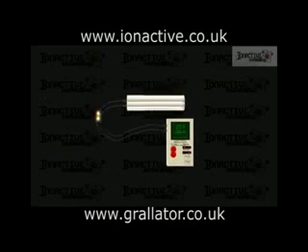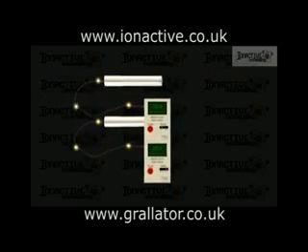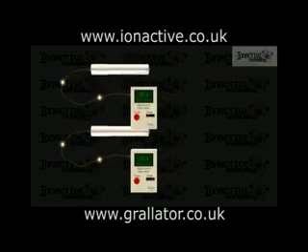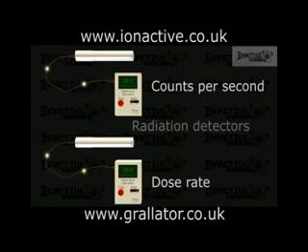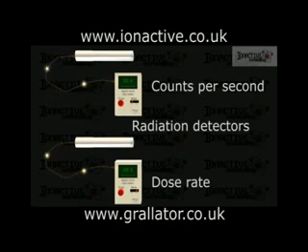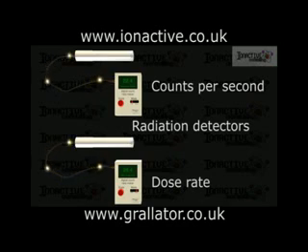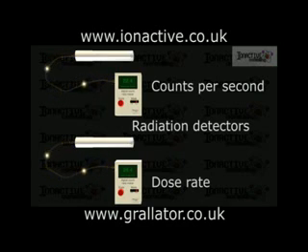The use of counts per second or dose rate will depend to a large extent on the circumstances of use. In both modes, radiation is being detected. In the former, the activity is displayed, while in the latter, a conversion is made to indicate the energy deposition rate.